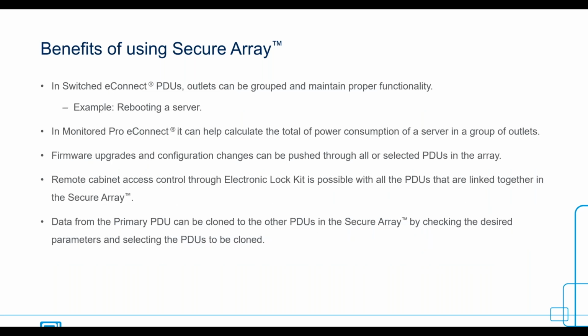Other benefits of using secure array can be found in our Switched eConnect PDUs. Here, the outlets can be grouped and maintain proper functionality. Think of when rebooting a server. In Monitored Pro eConnects, it can help calculate the total power consumption of a server in a group of outlets. Firmware upgrades and configuration changes can be pushed through all or selected PDUs in the array.